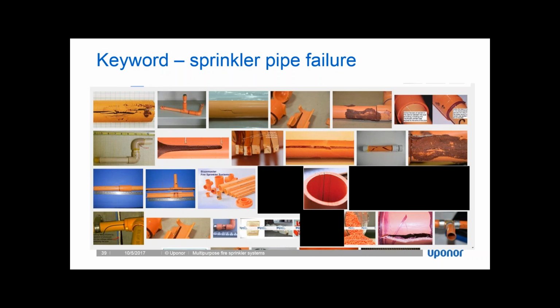And I always say, how do you know that the pipe you just got from the wholesaler isn't damaged already? My contention is that by the time you install CPVC, you're already installing damaged pipe. So you need a durable product when you're doing fire sprinkler installation. It doesn't matter if you're doing a green multi-purpose system or a standalone system, you want a pipe that is durable.